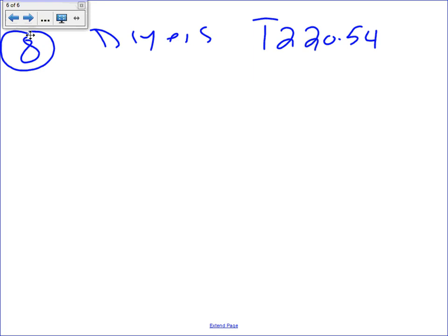Nick, what was the size I gave you? Did I give you guys 6.5 for each dryer? 6.5. So let's go to this table first and see what 220.54 says. Now, how many dryers do I have? I have 30 of them. It says 24 to 42. Now talk about jumble, look how they say it. Okay, let's take 30. I have 6.5 kVA.